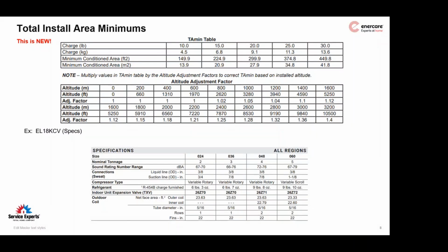I use the EL18KCV, the new R454B low GWP equipped single stage air conditioner, from their Elite Series variable model. You can see the refrigerant weights as the units have been produced and shipped in the specs on the chart below here. Where that arrow is pointing, even up to the 5-ton model all the way at the far right, they all ship with less than 10 pounds and will allow for up to the standard 15 feet of line set that Lennox traditionally does. Carrier's the same way, Goodman is the same way, 15 feet of line set before you've got to add any additional charge.